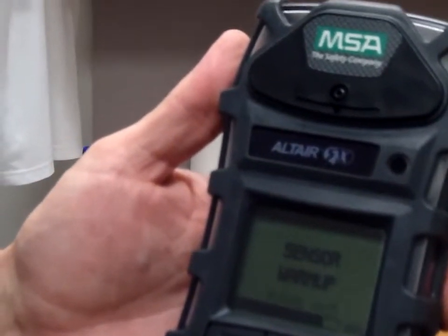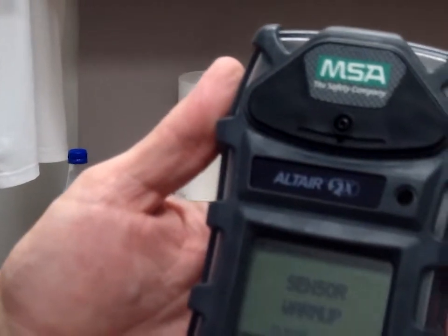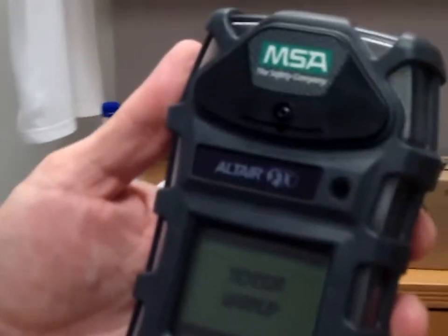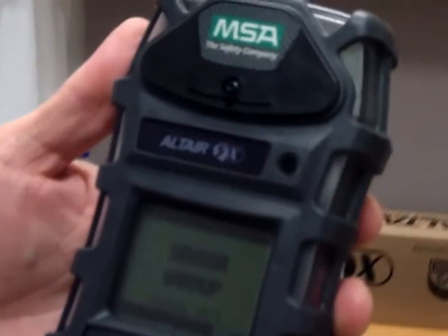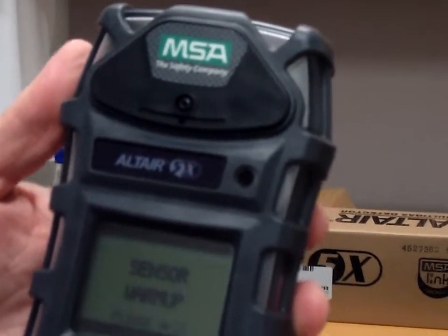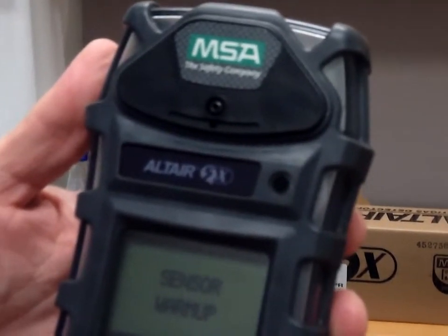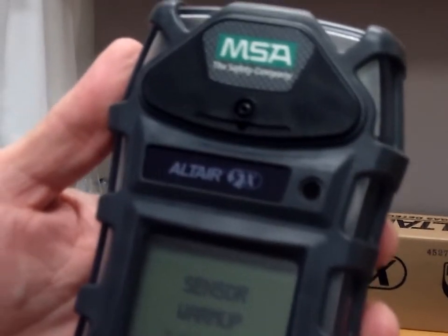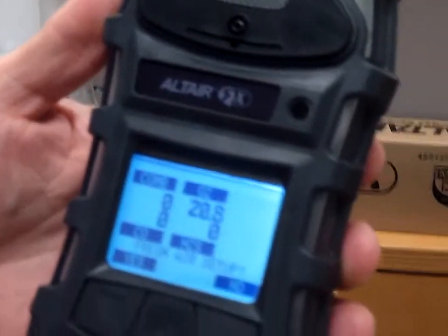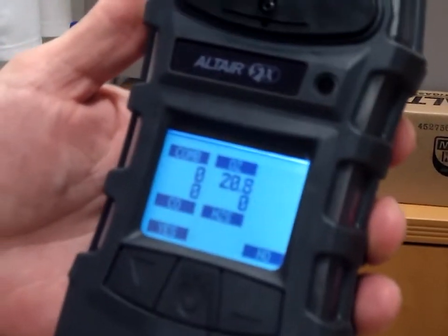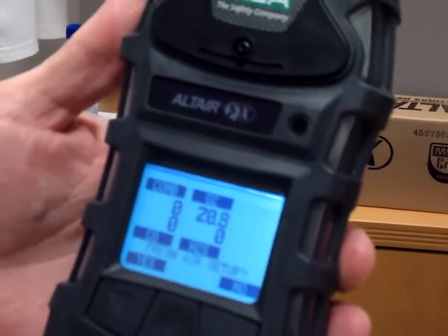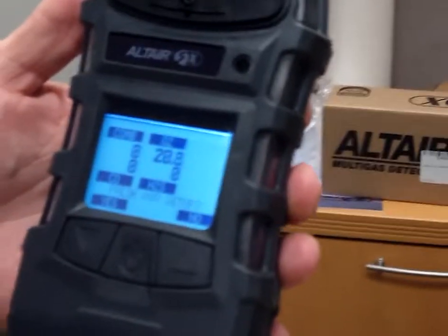That is all preset in there and all pre-programmed, so you don't have to do any adjusting or any fitting or anything like that. You do want to make sure, though, on those calibration set values that any calibration gas that you're using is those values. Mm-hmm. Okay, so that's 58% LEL combustibles, 15% oxygen, 60 ppm CO, and 20 ppm H2S.